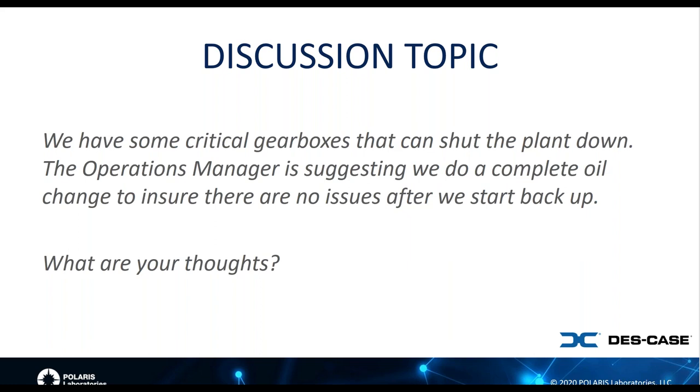Yeah, the other thing I would add there is, we see this even under normal circumstances where equipment is running under normal operating conditions. You take a sample, you send it to the lab. The lab runs a series of tests, including perhaps a particle count, and the report comes back and it states, hey, the oil here is dirty, and the first thing that somebody thinks about doing is changing the oil. And sure enough, they initiate an oil change, and maybe a month later, we submit another sample to the lab. The same thing happens. We get a report back that says the oil is dirty, and it becomes this vicious cycle.